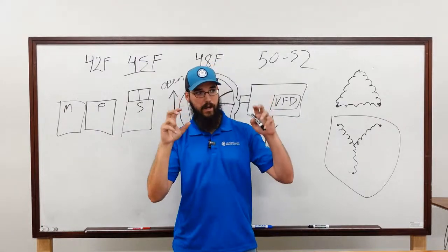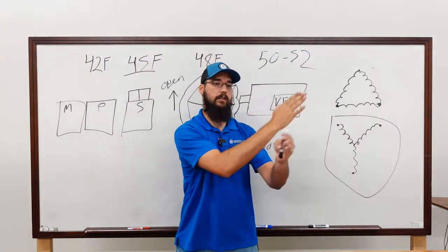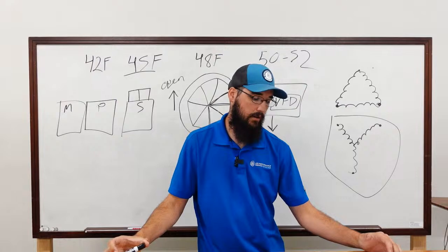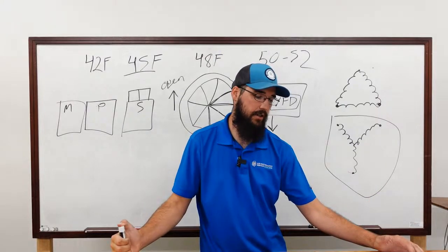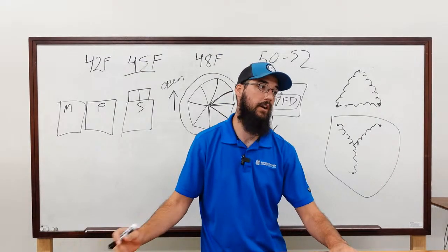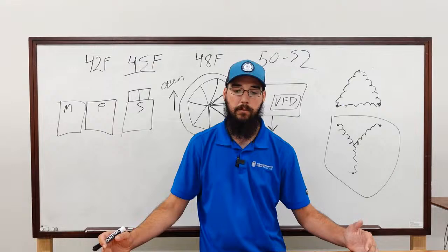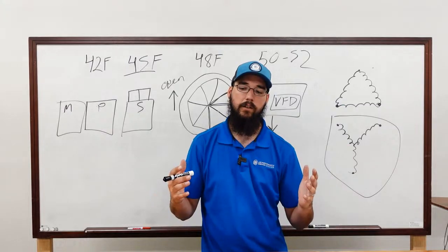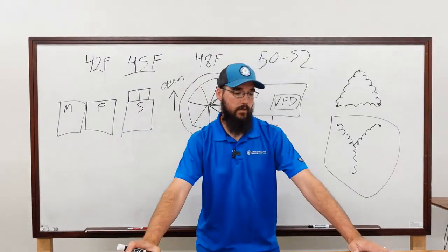The triac core inside of there just locks to what would be a closed or positive state to send that power through to the motor. So it's able to run as if that component was just straight across the line. It doesn't have the cooling capacity or the controls. That technology wasn't designed for it, so it doesn't have the capacitor bank or the inverters or anything else in there to do what VFDs do. It's a solid state control system that just slowly ramps the motor up, but it uses very similar principles to what a VFD does. Again, if you're familiar with SCR heaters, then you should have a fairly good understanding of a solid state starter.